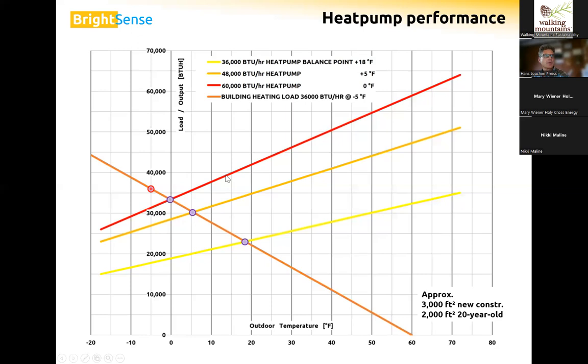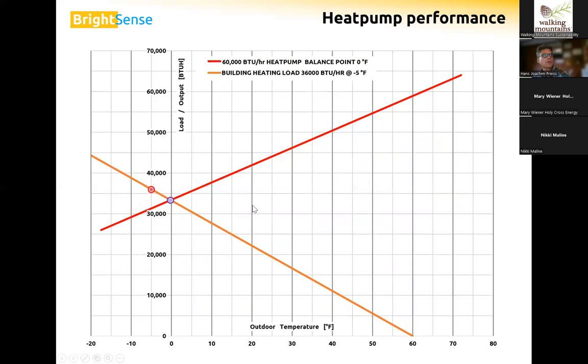And I should mention, this is typical. People might ask, so what is the heating load of 36,000 BTUs at negative 5? What kind of a home is that? It would roughly be a 3,000 square foot home if it was a new construction today, or if it's a 20-year-old home, roughly a 2,000 square foot home would have about this load in our climate zone.